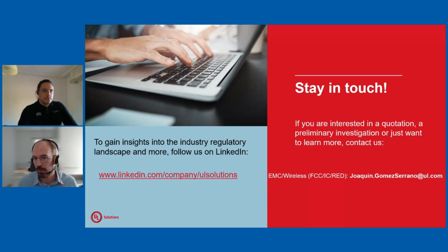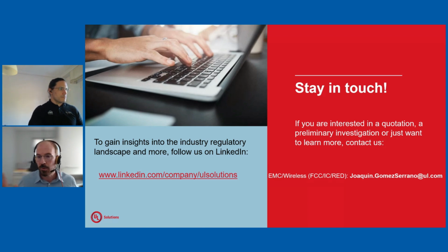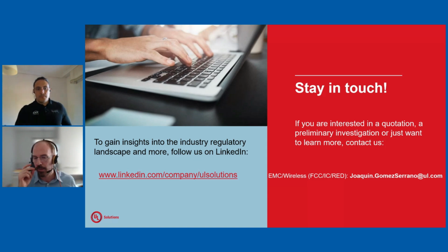When it comes to radio, it's even more so, because FCC and Canada are very formal. They will only accept test reports performed against the FCC and Industry Canada standards. FCC and Industry Canada will never accept reports coming from a European standard that may be very similar in terms of the way of measuring. They will not accept it because of multiple factors, and one of them is the way we do the setup and the way we do the measurement, which will be very equivalent, but this is not acceptable.